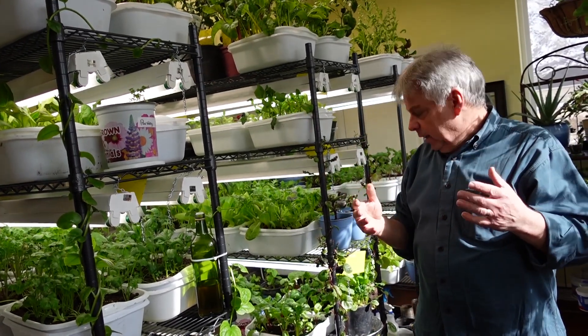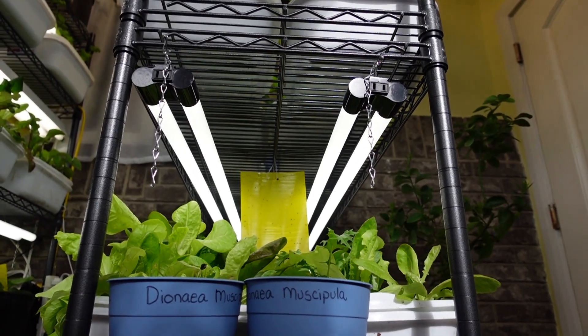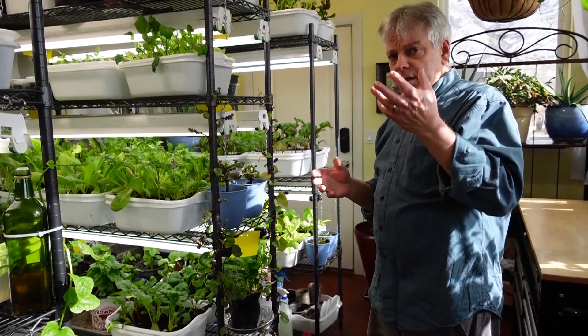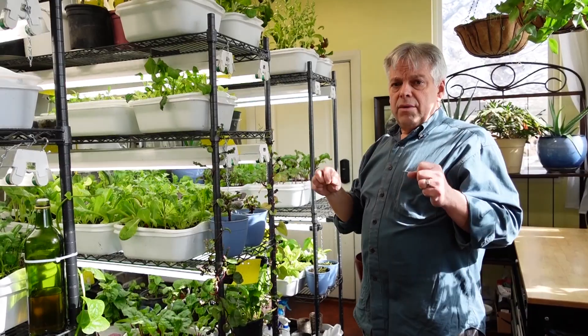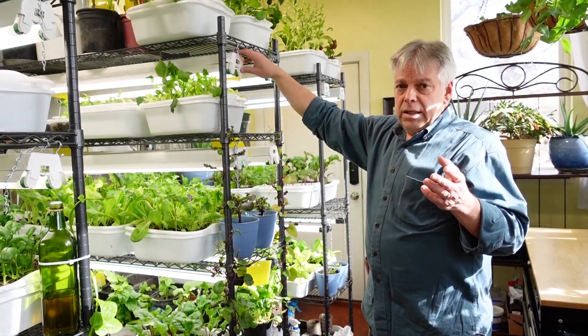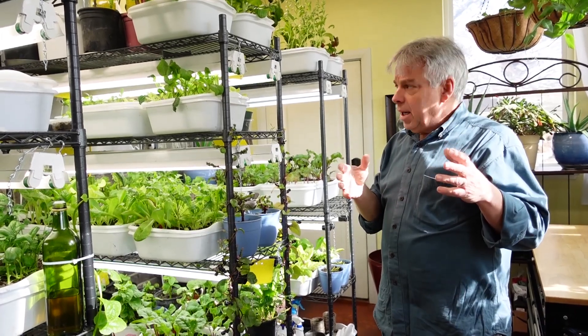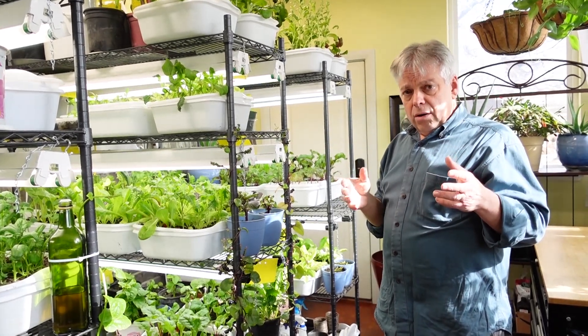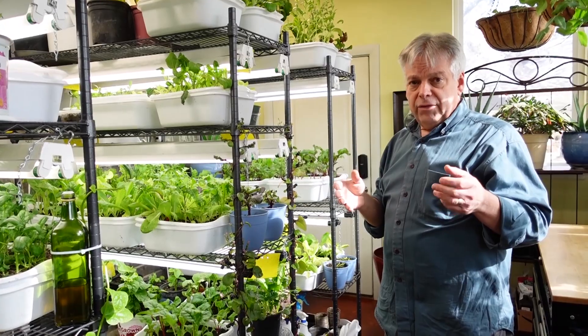We also have some LED lights — you can see some of those here. These typically run about 18 watts per bulb, so 18 watts instead of 28; that's a fairly considerable power savings. We've also converted some of these shop lights into LED using a ballast bypass A+B kind of bulb. Those are working out fairly well, and they're going to use less energy than the fluorescents with a much longer lifetime.